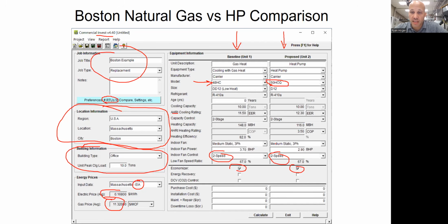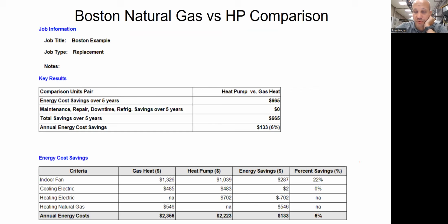One thing you will notice is that the fan horsepower is different on here. These are the same unit in the same cabinet, same compressor, same cooling coil, but I have lower fan horsepower on the heat pump. That is normal. Gas-fired equipment requires a fan that can do more air movement. I shouldn't say more, but it requires more energy to move the same amount of air because I have to shove the air through the evaporator coil, then I have to shove the air through the gas-fired heat exchanger coil. So it takes more horsepower to do that. So I'm going to save fan energy by doing a heat pump versus a gas heat system. And my efficiency also improved for the same reason. The efficiency level includes the fan energy, so the cooling side also improved.